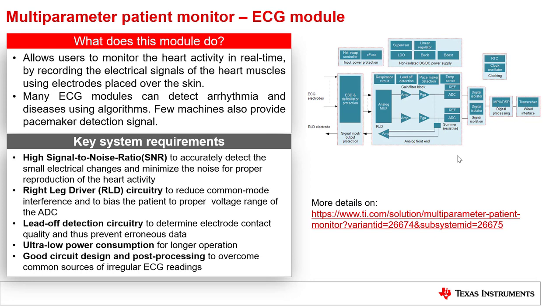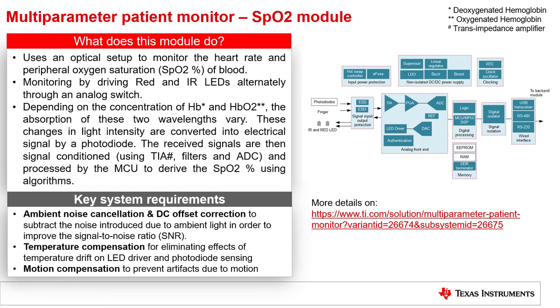The second module is the SpO2 module. This module uses an optical setup to monitor the heart rate and peripheral oxygen saturation, or SpO2 percentage, of blood. The monitoring is done by driving RED and IR LEDs alternatively through an analog switch. Depending on the concentration of HB and HbO2, the absorption of these two wavelengths vary. These changes in light intensity are converted into electrical signals by a photodiode. The received signals are then signal conditioned using TIA, filters, and an ADC, and processed by the MCU to derive the SpO2 percentage using algorithms.